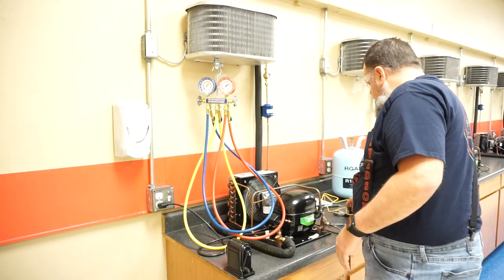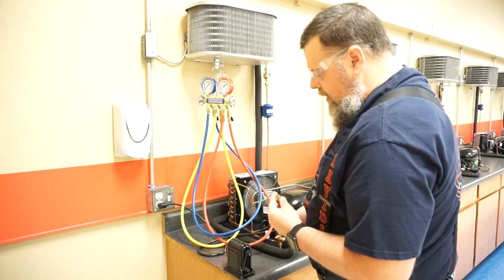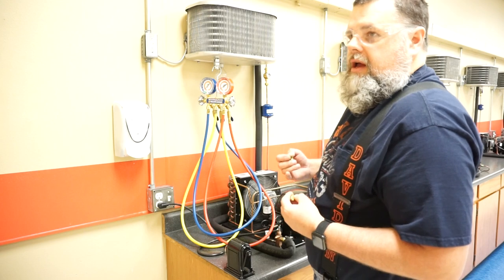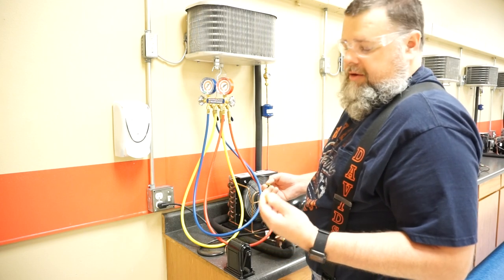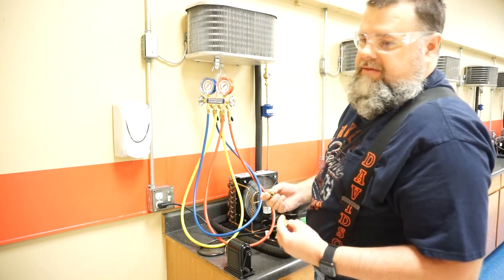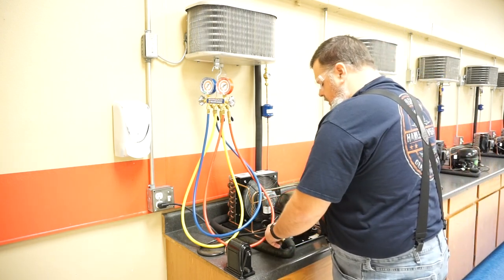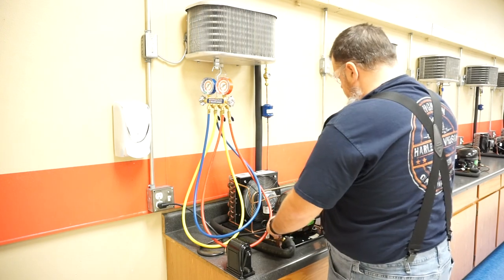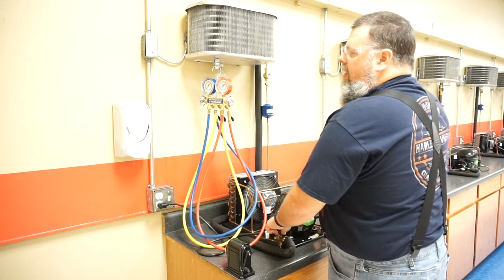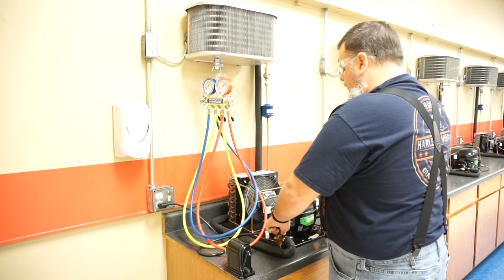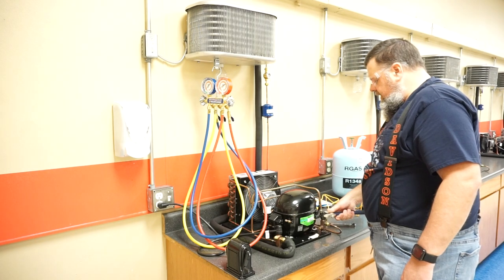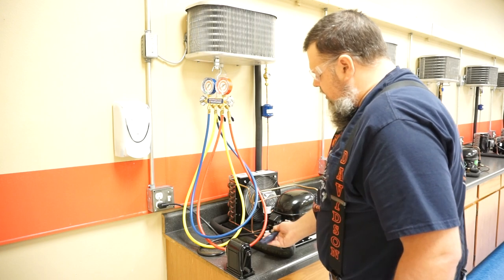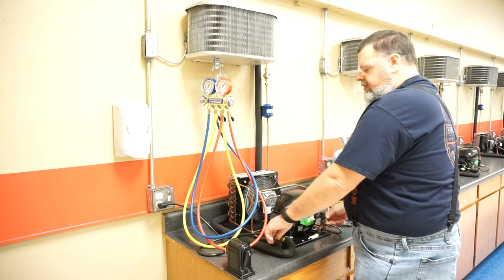Now for this system, I want to make sure I put back on these caps. Because if it's going to leak, it's going to leak around these points. It shouldn't leak with a brand new system, but the more you play with these valves in the field, they probably only get worked on maybe once a year. Here, this is on a daily basis, so they tend to wear out. So I want to put my caps back on. It's going to keep my refrigerant from leaking out. I'm going to put these back on for my stems. I want to keep my stems nice, out in the weather and stuff they get cracked, dried out. I just want to give this a little bit of a snug. I want to do that so I can't just take things off with my fingers. That way I know it's extra together.